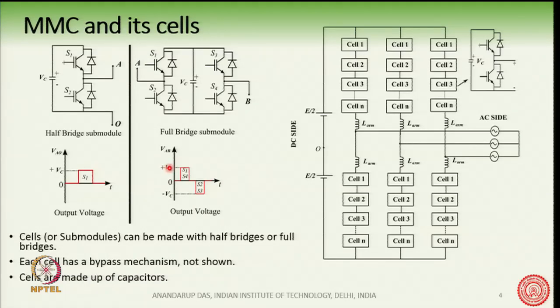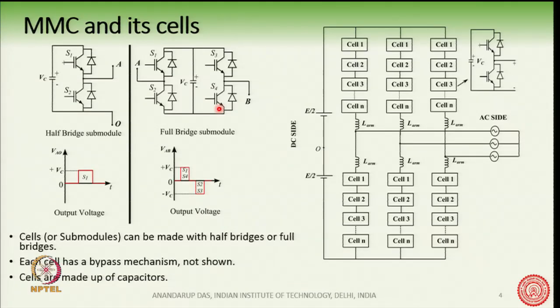For the full-bridge sub-module: turning on one diagonal pair gives +V_C, turning on the other diagonal gives −V_C, and turning on S1 and S3 or S2 and S4 gives 0 voltage at the output. So with half-bridge cells we get two voltage levels (0 and V_C), whereas with full-bridge cells we get three levels: +V_C, 0, or −V_C.